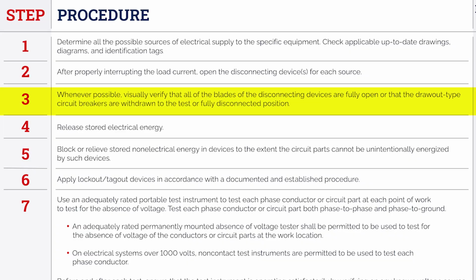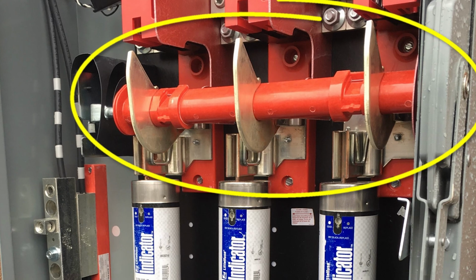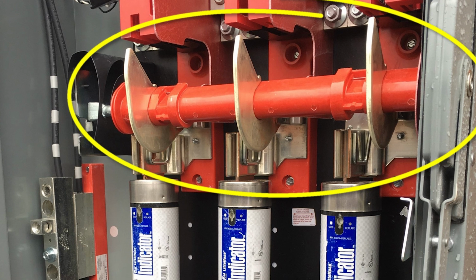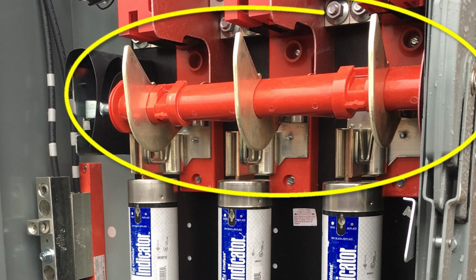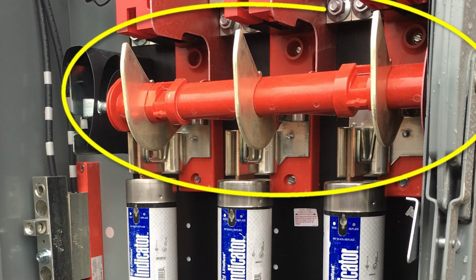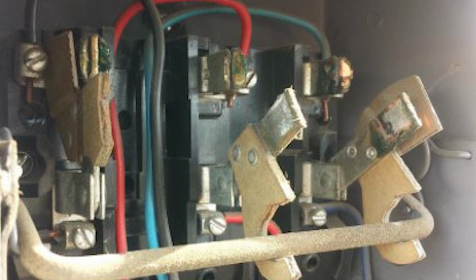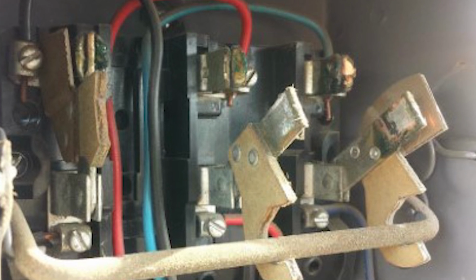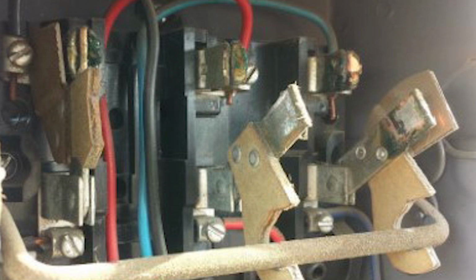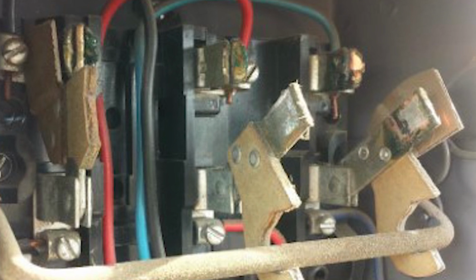All right, moving on to step 3. Step 3 tells us that wherever possible, you need to visually verify that all the blades of the disconnecting device are fully open, or that draw-out type circuit breakers are withdrawn to the test or fully disconnected position. Here's an example of why that's important. If you just shut a disconnect off, lock it out, and then go downstream to do your work, you could be shocked or killed by this oversight. Visually verifying it is a very important step.